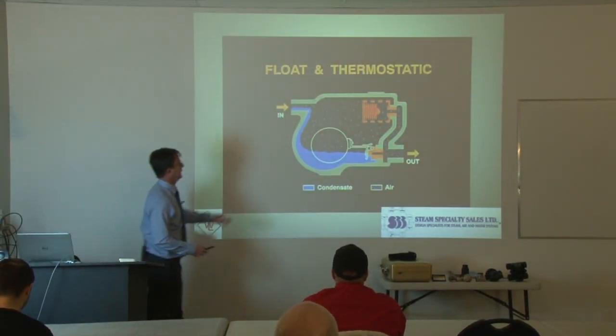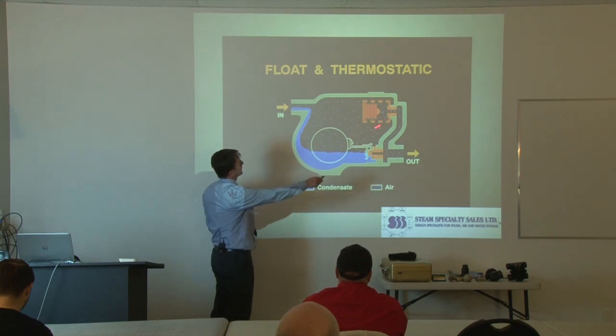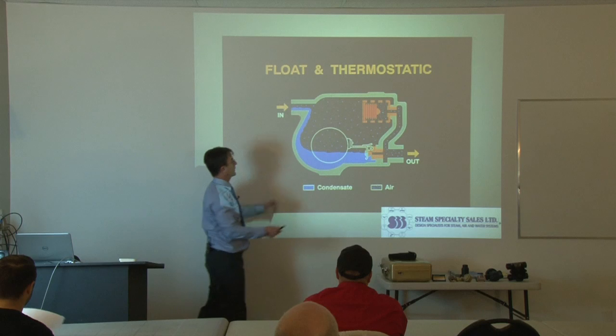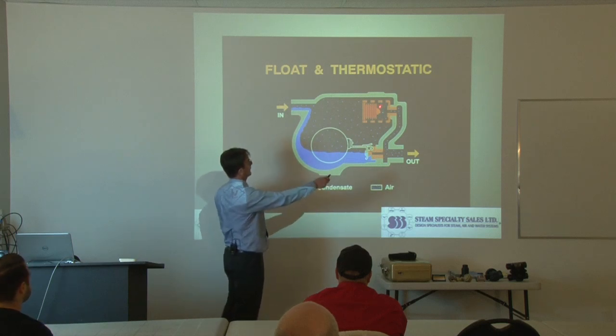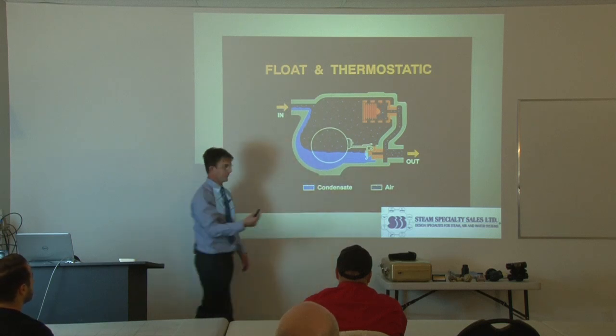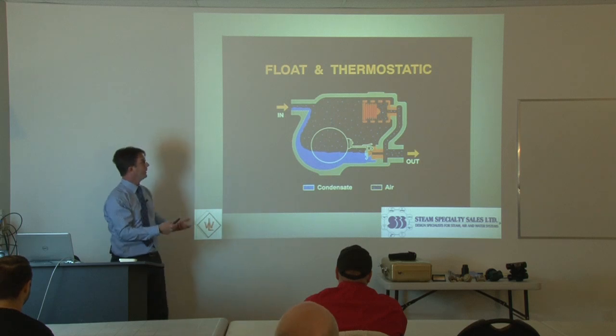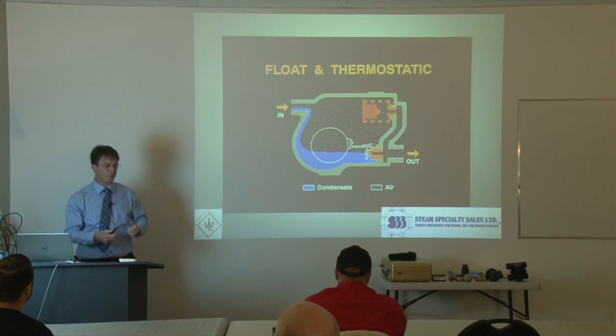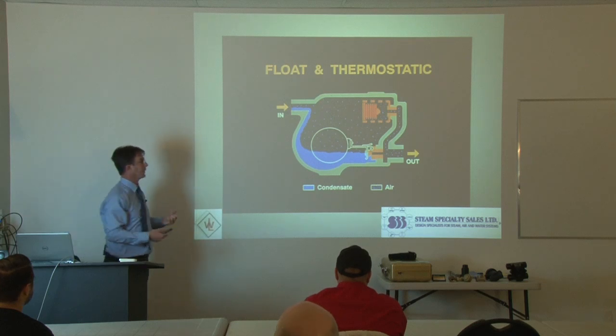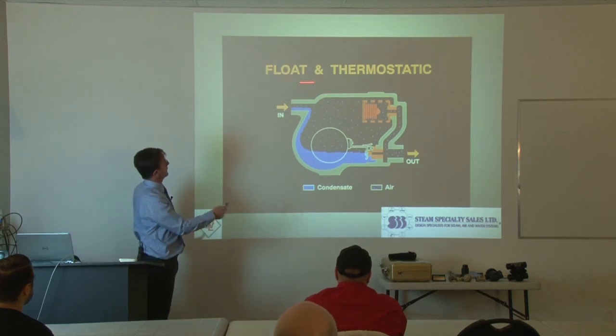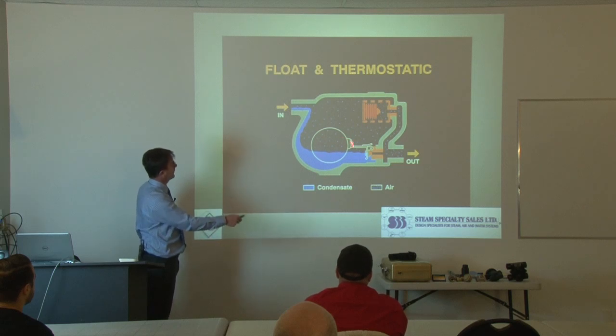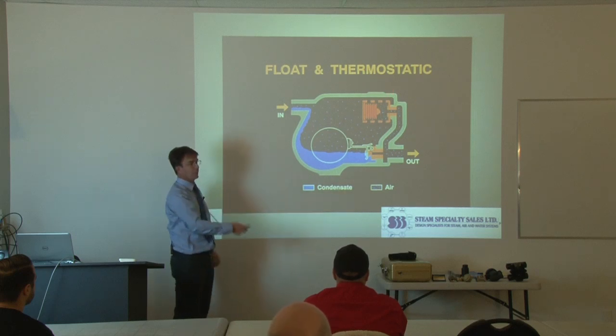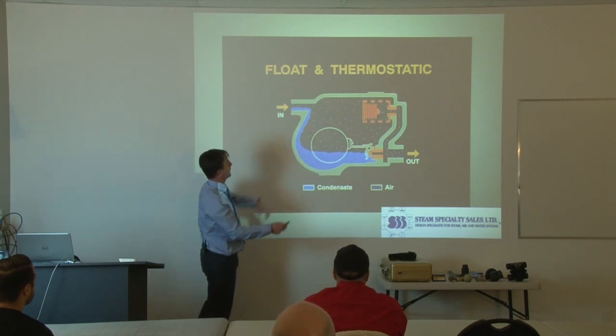The float and thermostatic — this is a bit of an older picture showing a bellows. Modern steam traps won't have that large an air vent; it's now a smaller stainless steel capsule, but the principle is the same — a liquid-filled device that expands or contracts depending on temperature. As the name implies, you have two operating devices: a float, which is the main device that lets condensate out, and a thermostatic element.